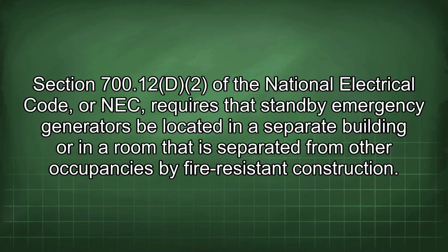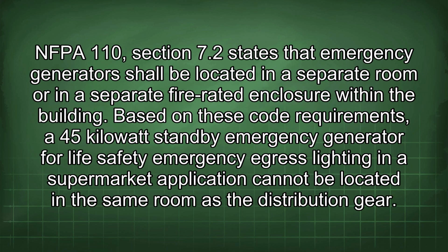Section 700.12 D2 of the National Electrical Code, or NEC, requires that standby emergency generators be located in a separate building or in a room that is separated from other occupancies by fire-resistant construction. NFPA 110 Section 7.2 states that emergency generators shall be located in a separate room or in a separate fire-rated enclosure within the building.